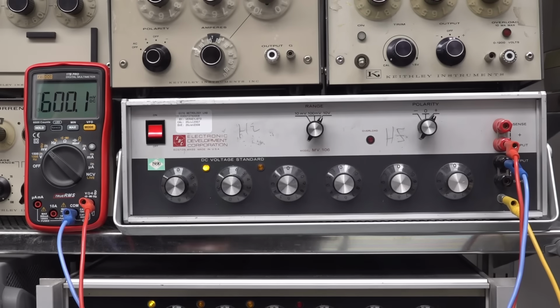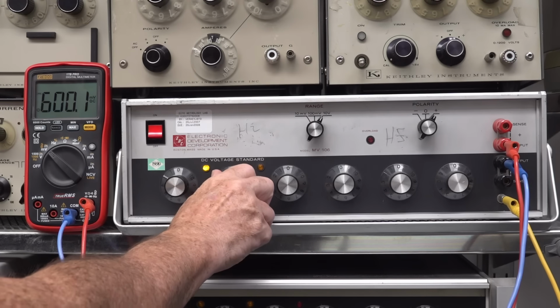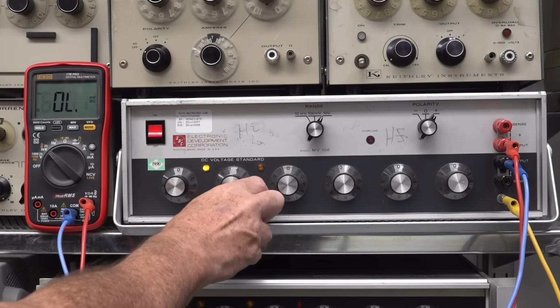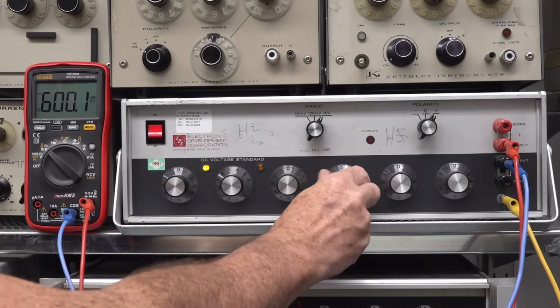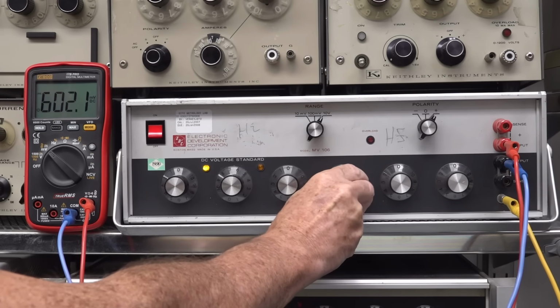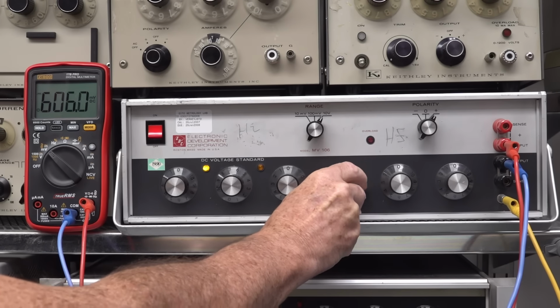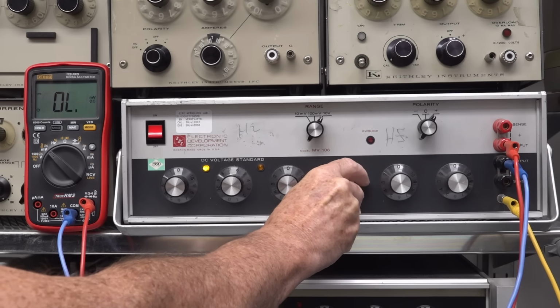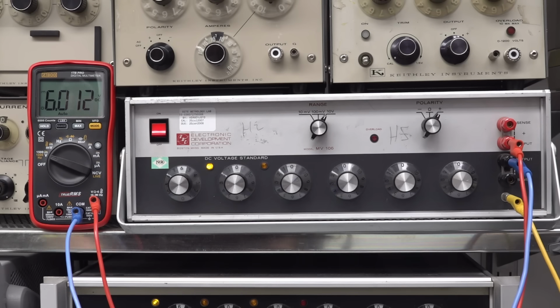600 millivolts, check. How far can we go above that? Can't go to 700. Ooh, can't go to... 6.1, here we go. How many counts? There you go, well, yep. Wow, the 6 volt range significantly out, look at that, 12 counts out. But actually that's within spec, that's still 0.2% at 6 volts. So that's interesting.